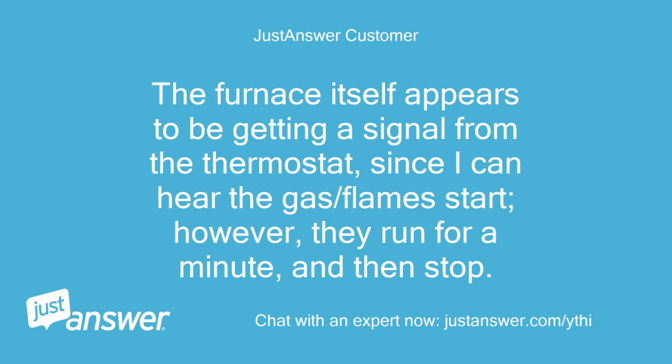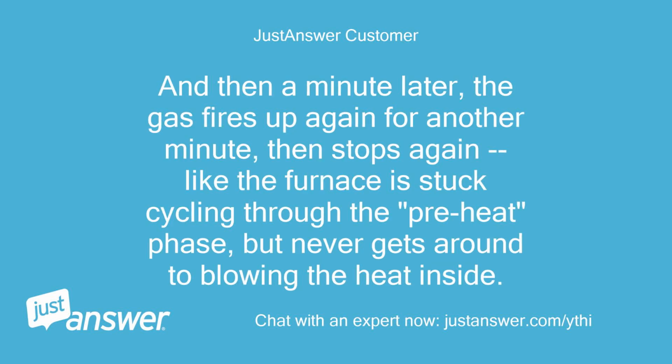The furnace itself appears to be getting a signal from the thermostat, since I can hear the gas/flame start. However, it runs for a minute, and then stops. And then a minute later, the gas fires up again for another minute, then stops again, like the furnace is stuck cycling through the preheat phase, but never gets around to blowing the heat inside.